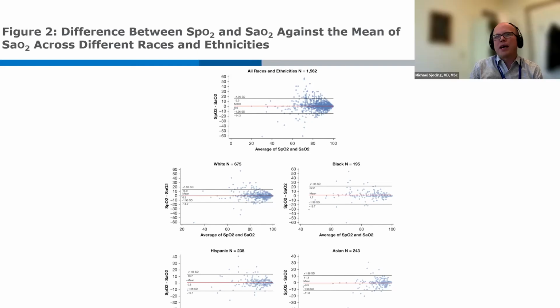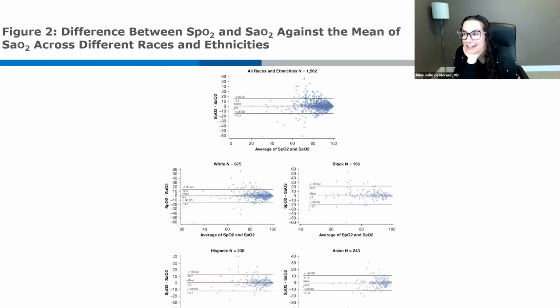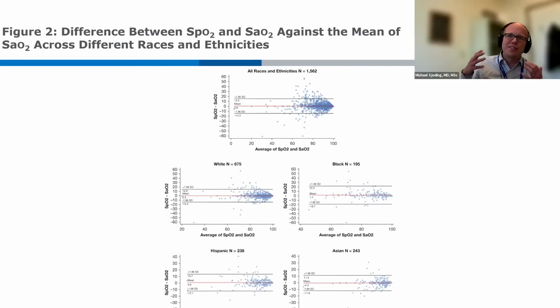For the melanin mechanism, one potential differing type of pulse oximeter, since most pulse oximeters are clip-on, right? They clip onto your finger, your ear, or your nose. There is a group of pulse oximeters that are stick-on, called reflectance pulse oximeters, where the light goes in and then reflects back off. So it's possible that group may work differently, but probably even in that group it's the same principle, the same issue. Melanin causes light scatter such that, as the two wavelengths are being recorded, the calibration is such that the accuracy is lower in darkly pigmented patients. So it's thought to be a class effect, and it wouldn't matter depending on where the pulse oximeter is being measured from.